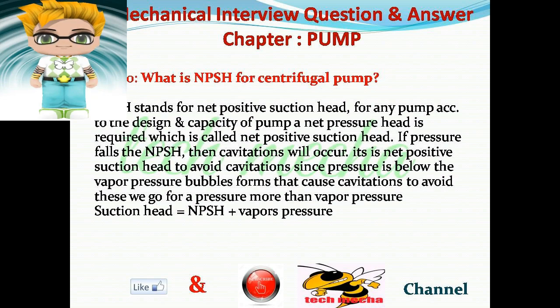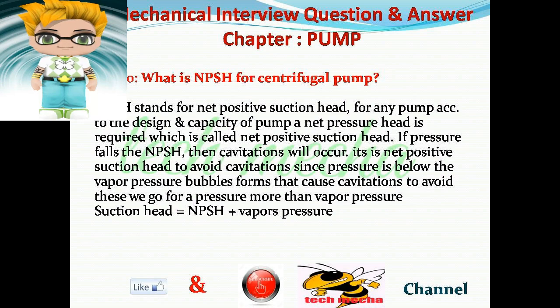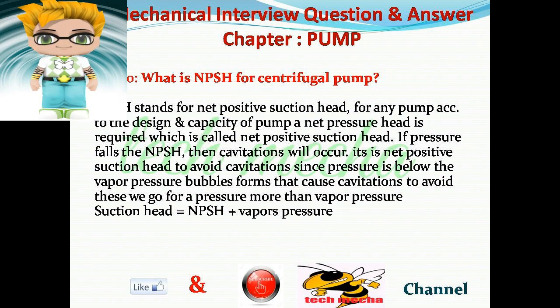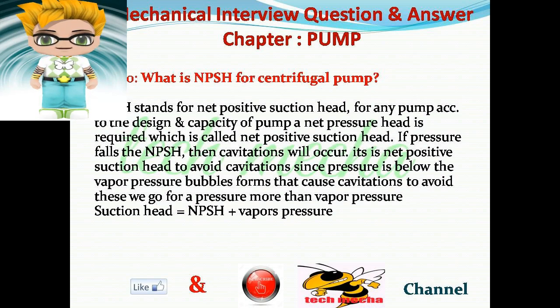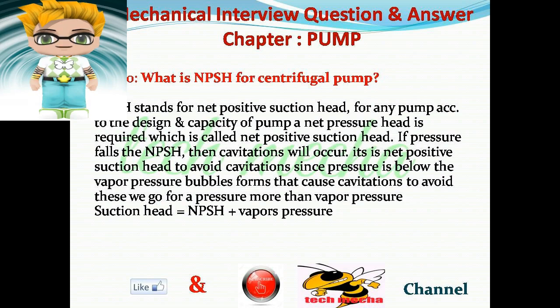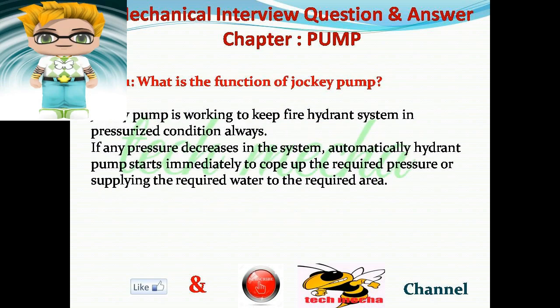Question number 10: What is NPSH for a centrifugal pump? Answer: NPSH stands for Net Positive Suction Head. For any pump to act at its design capacity, a net pressure head is required, which is called the Net Positive Suction Head. If pressure falls below the NPSH, cavitation will occur. NPSH is required to avoid cavitation; since pressure below vapor pressure causes bubbles to form, we maintain pressure above vapor pressure.